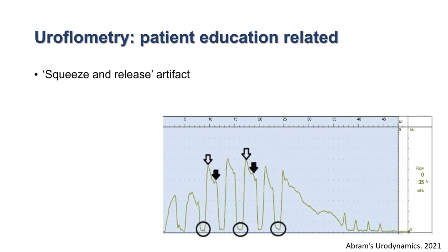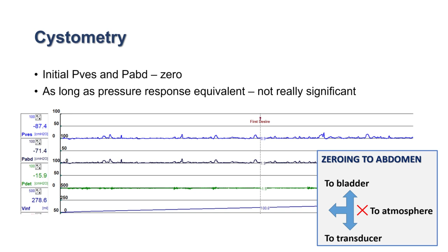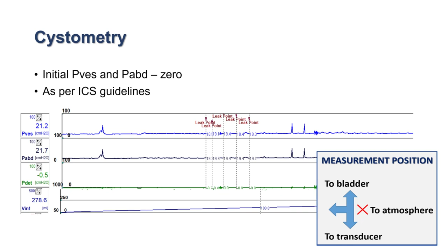Now, in cystometry, if the initial P ves and P abdomen are zero, that is, the zeroing has been done to the bladder and the rectum and not to the atmosphere, it can be considered an artifact as per ICS guidelines. As long as the pressure response is equivalent, it's not really an artifact, as you can see in this study. However, we go by ICS and zero to atmosphere and then activate the organ, and we will get a baseline P ves and P abdomen which is higher than zero, and the P det will be subtracted to be zero.